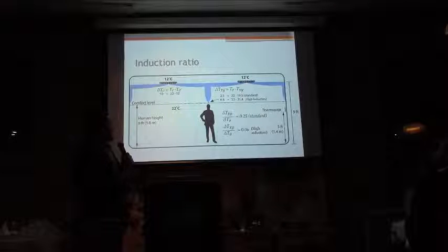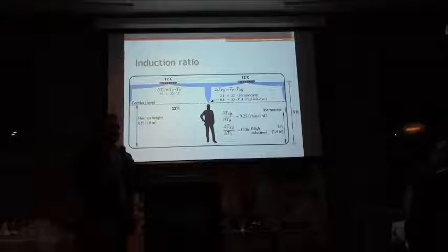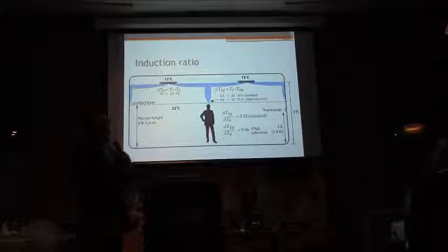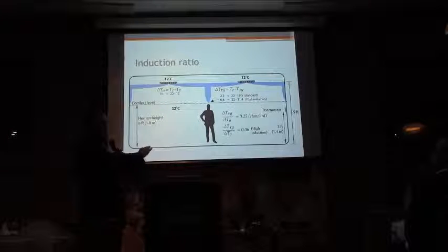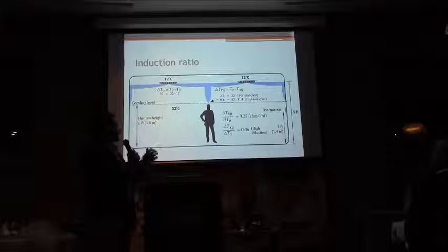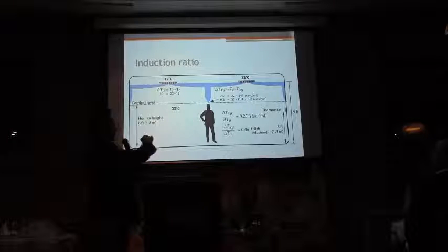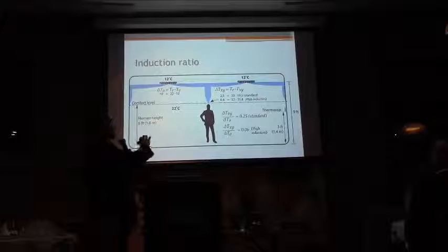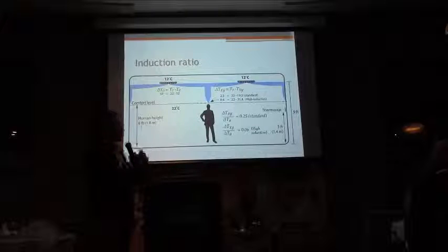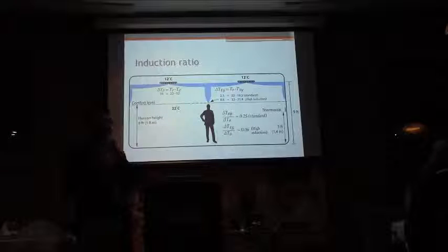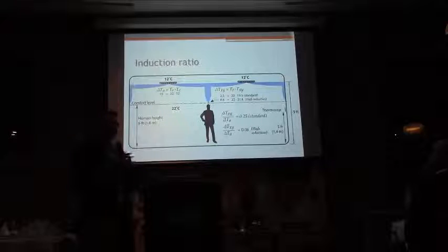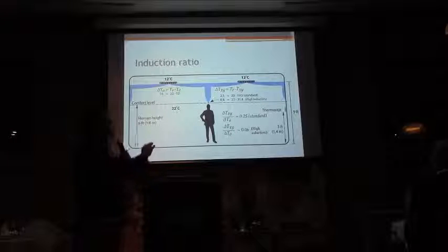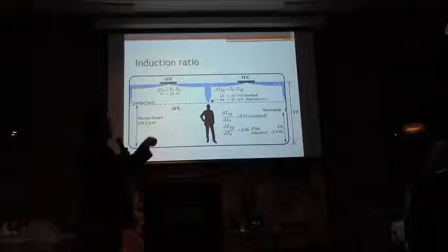So in Europe, instead of ADPI, what they use is induction ratio. And that's not recognized by ASHRAE. But it is a good way to determine the efficiency of your HVAC, of your ventilation, both in cooling and heating. Because all it is basically is a bunch of temperature readings across the room.